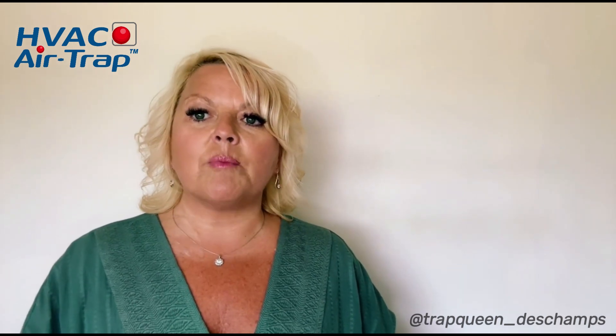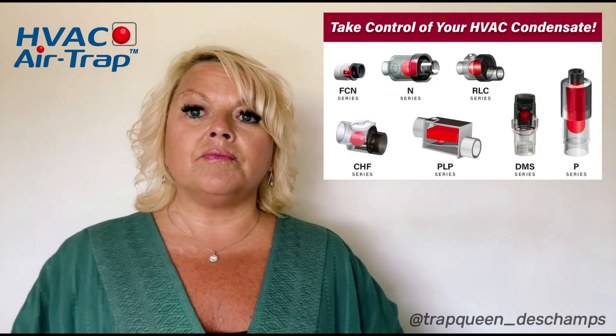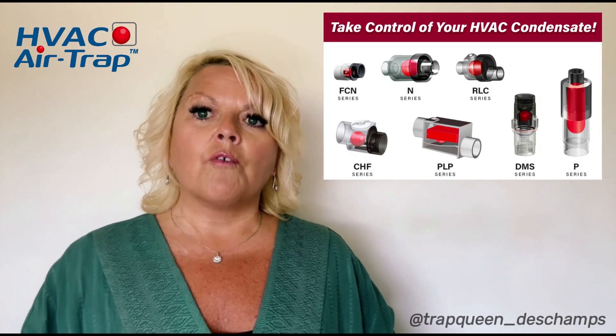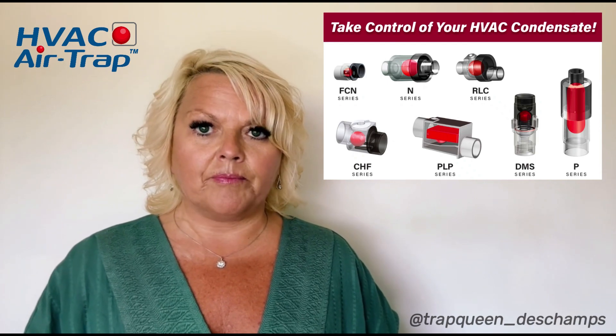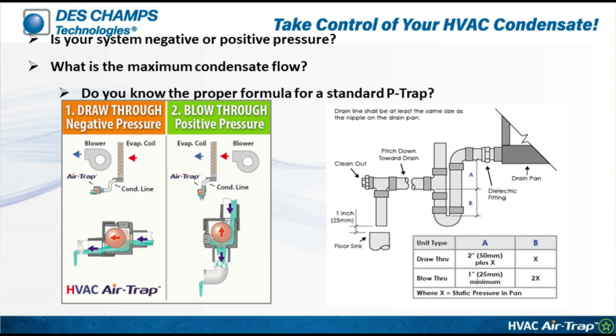And that's when the standard P-trap fails. So what is a better solution? For a negative pressure system, the standard P-trap formula is: take the static pressure of the system, times two, plus one, to get your height. So for example, if you have a two-inch static pressure, that means you need a four to five inch drop for a standard P-trap. Now, the solution we're going to talk about today is called the air trap.